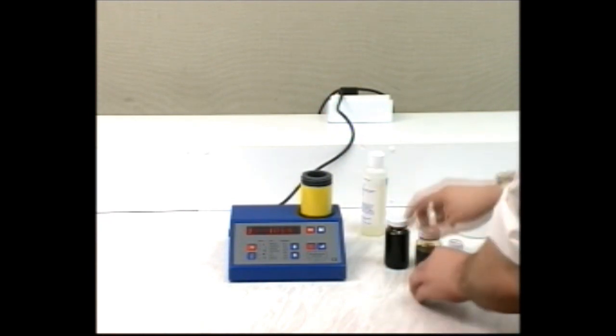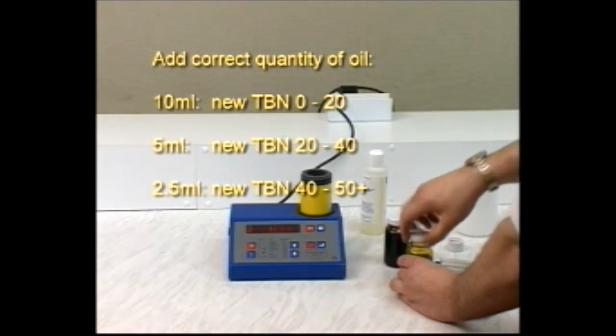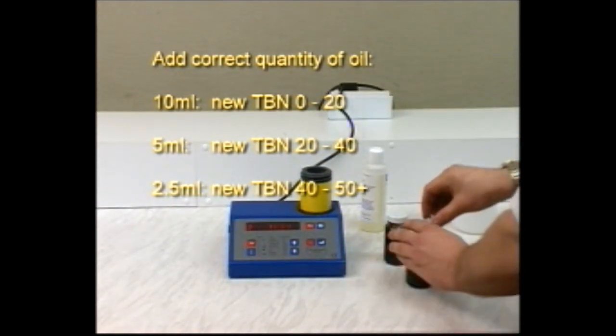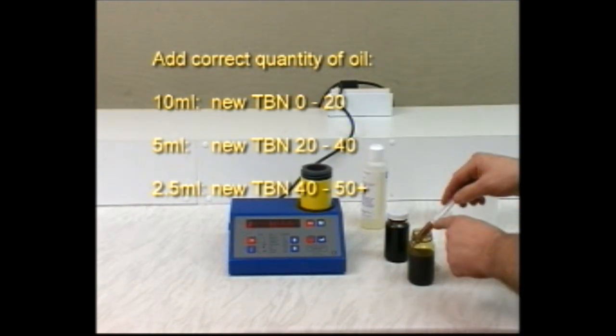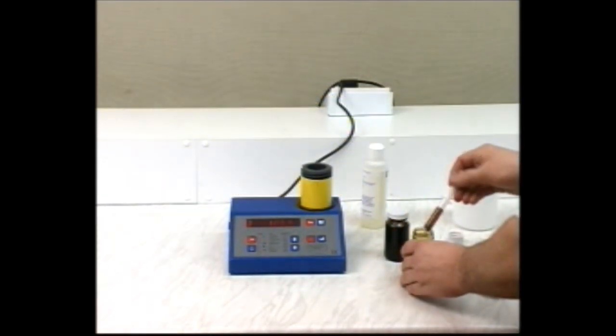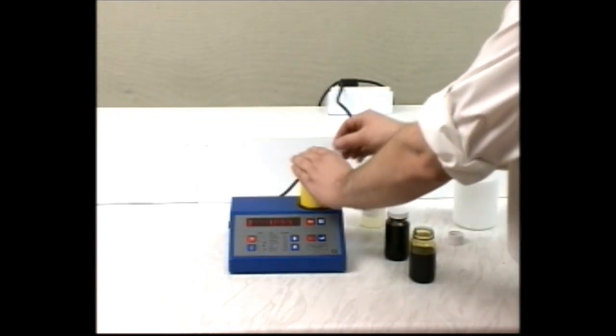Add the correct quantity of oil: 10 mL for a TBN of 0 to 20, 5 mL for a TBN of 20 to 40, 2.5 mL for a TBN of 40 to 50. Replace and tighten the end cap.